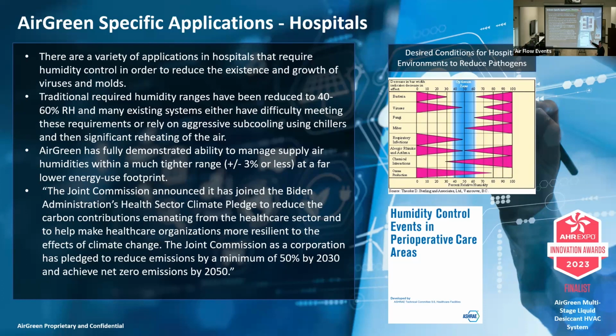So, just another application that we've been engaged with. One of the hospital chains asked us to get involved with a demonstration program with them. Operating rooms have a range of humidities they like to operate. It's cold and it's dry, and they have actually finally just written code to bring it into that 40 to 60. It was broader than that before. And we think, particularly in southern climates, putting us on the front end of existing systems is really smart. They're small, compact, standalone. And from a hydronic system standpoint, most of those facilities will have a central plant where they have chilled water and hot water available. There is a huge sustainability movement in hospitals.